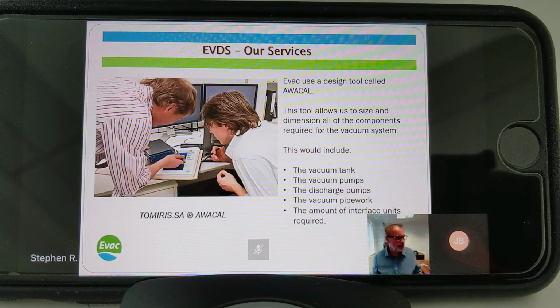I take all the information from you guys on flow rates and expected use, feed that into our design tool, and that gives me everything needed to size the tank, the pumps, the pipe work, and the number of interface units required. I take all that away from you. The only thing I can't do is coordinate the pipe work, but you guys would be doing that anyway.